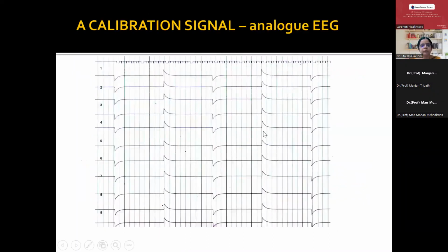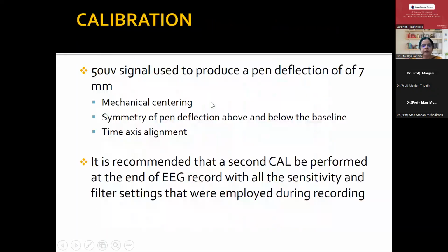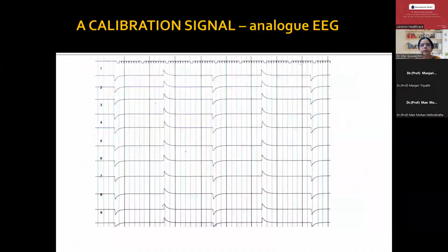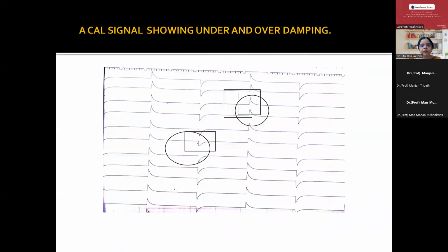So this is an example of a mechanical calibration in an analog machine, where you give this 50 microvolt signal so that the pen deflection is around 7 millimeters, and all the pens should be deflected equally and all the electrodes should react in a similar way. If the pens are not aligned properly, one can get something called under damping or over damping. The lower one is an example of under damping, and the upper one is an example of over damping.